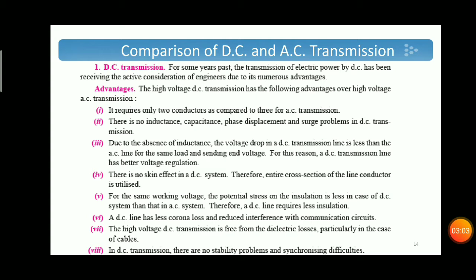And the potential stress on the insulator will be less in case of DC for the same working voltage. So the insulation requirement is also less. A DC line has less corona effect and the frequency is 0. It reduces the interference with communication circuits. And also the high voltage DC transmission is free from dielectric losses, particularly in case of cables. In DC transmission there are no stability problems as frequency remains constant. There is no synchronizing issue or stability problem.